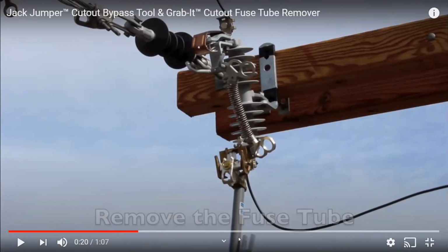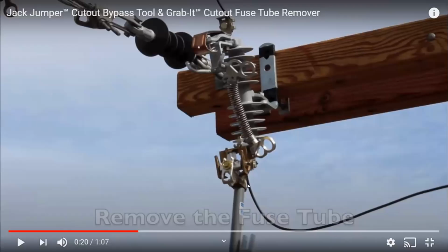We tried not to use these too much in underground, and you can see why. The underground terminator usually comes up in this area, terminates in here, and then the wire sits right in this area. And remember, the jacket that's on the outside of the cable, is it insulated or not? On underground primary cable, the outer jacket? It is not insulated. That's just a polyethylene protective cover, and they're trying to save money on conductor there. Right underneath that is the ground.